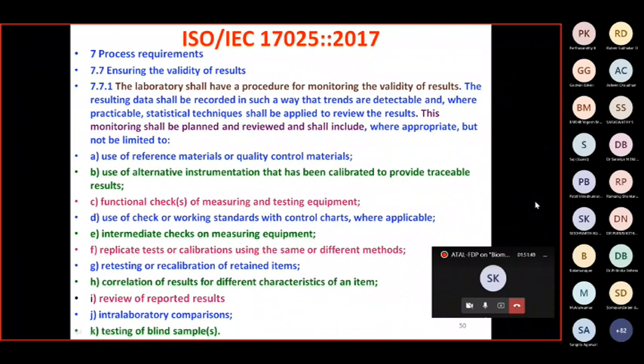And these two results will be evaluated, analyzed for congruity. If they are similar, if the errors are well within the permissible measurement uncertainty level, then fine. In case errors are larger, then deeper analysis is done to find out what has gone wrong. Testing of blind samples.